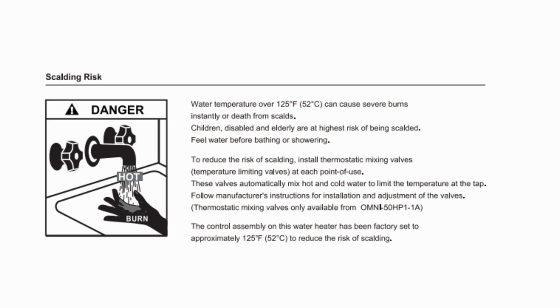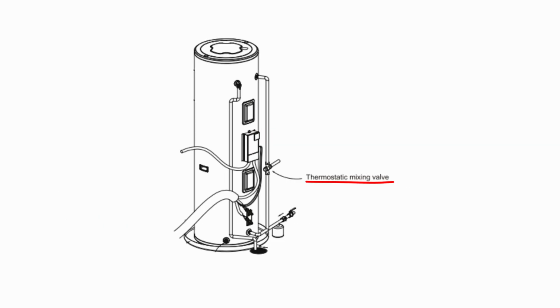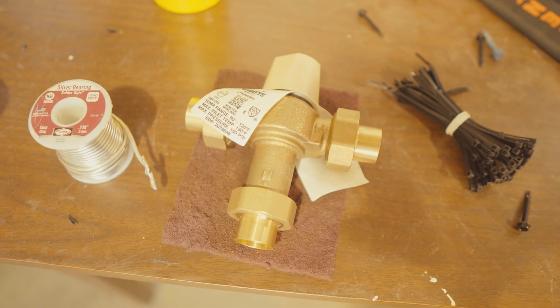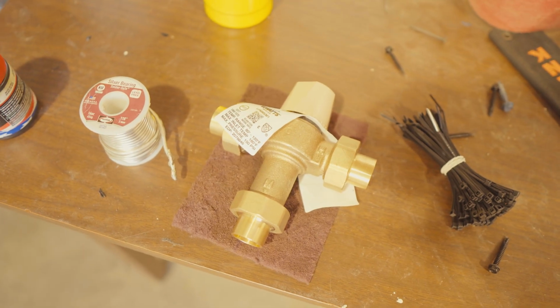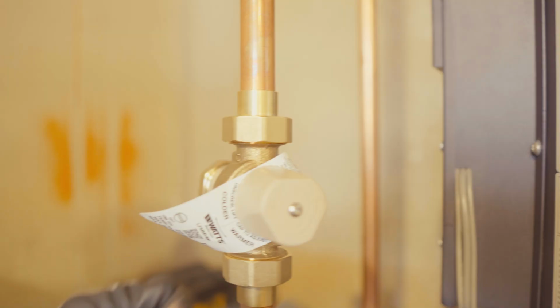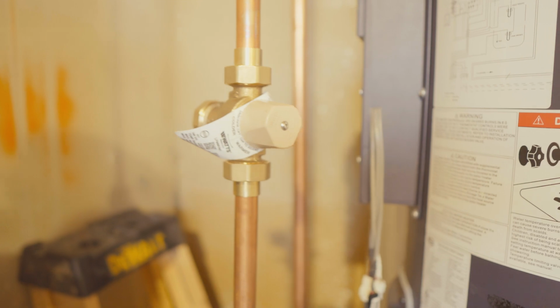Scalding risk. Water temperatures above 125 degrees F, 52 degrees C, can cause severe burns or even death in a very short time. To reduce the risk of scalding, install thermostatic mixing valves or temperature limiting valves at each point of use. These devices automatically blend hot and cold water to maintain a safe outlet temperature and provide consistent protection at the tap.